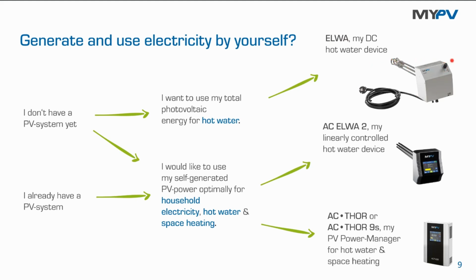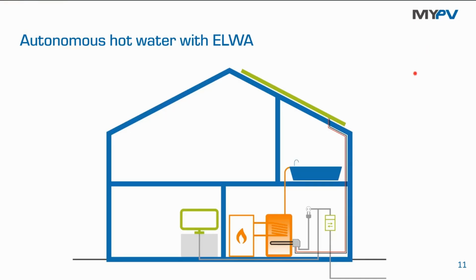The product with the gray cover is the only DC solution we have, so there are PV panels directly connected to the units, with no PV inverter in between. This means you have the same principle as a solar thermal system: you take all the energy from the roof and use it for hot water heating only. You cannot use this electric power for other appliances in the building, like the light or the TV—everything goes into heating only.